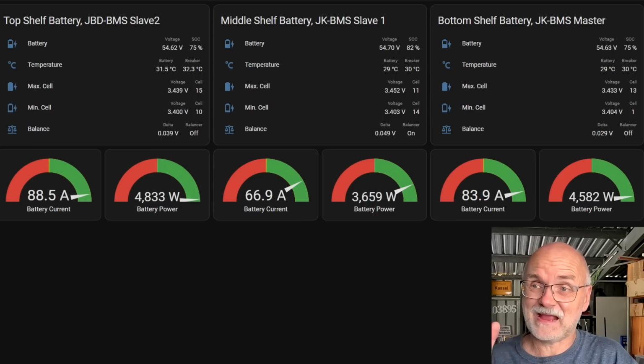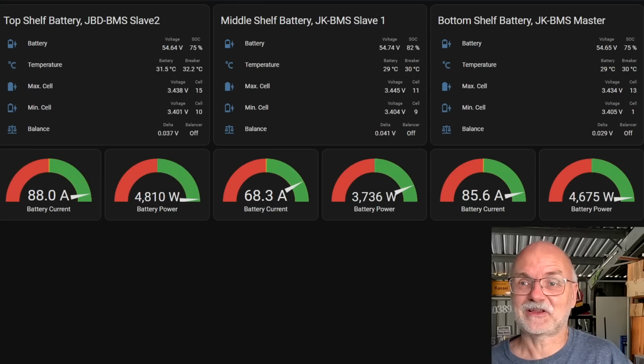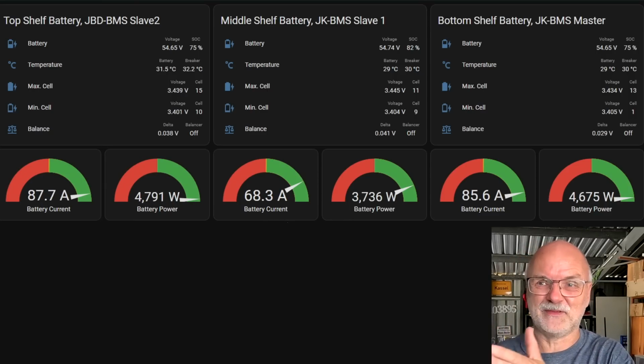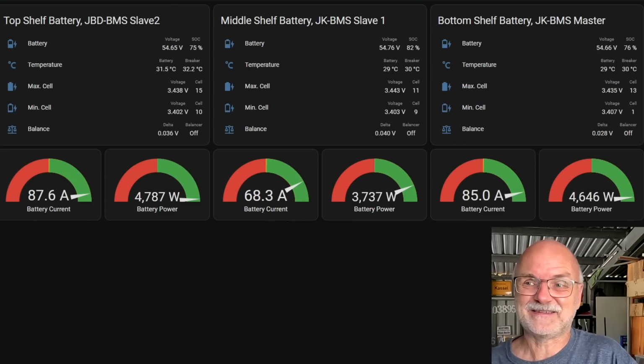This is probably the maximum I charge the batteries with, 80-90 amps, just for testing purposes. Clear result here, 88, 68, 85. This one should actually be right in the middle of these two batteries somewhere, but it is far lower, due to the higher resistance.